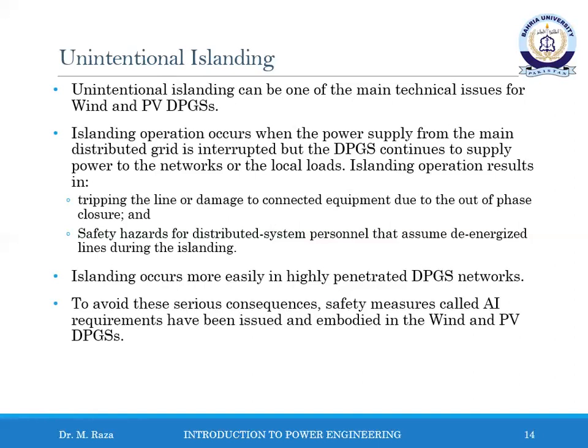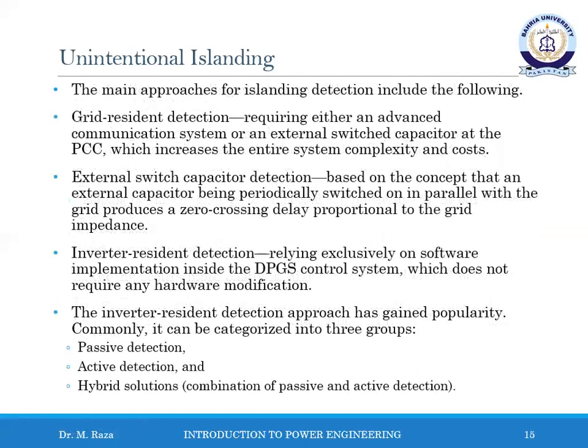Islanding occurs more easily in highly penetrated distributed generation system networks. To avoid these serious consequences, safety measures called AI requirements have been issued and embedded in the wind and PV distributed power generation system. The main approaches for islanding detection include the following. Grid resident detection, which requires either an advanced communication system or an external switched capacitor at the PCC, which increases the entire system complexity and cost.